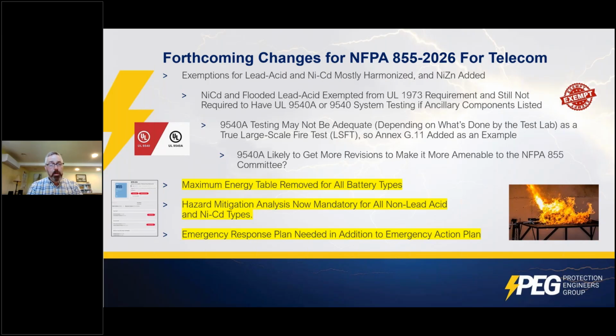They've struck the maximum energy storage table. Basically, there is no maximum limit anymore, but the HMA is now mandatory, and for chemistries other than lead acid, NiCad, and the aqueous chemistries, you need to do the fire testing anyway. So the MAQ table, the maximum allowable quantity table, has been removed, but there are other requirements that you have to do, hazard mitigation analysis and so forth, which is a good idea. That was a good change. I think it's important that every chemistry be analyzed and made sure it's safe using hazard mitigation analysis.